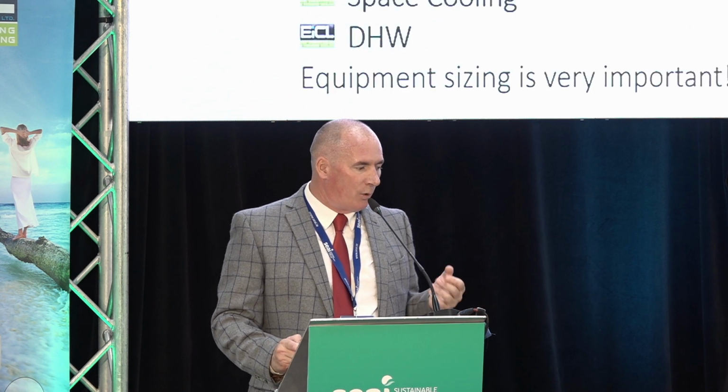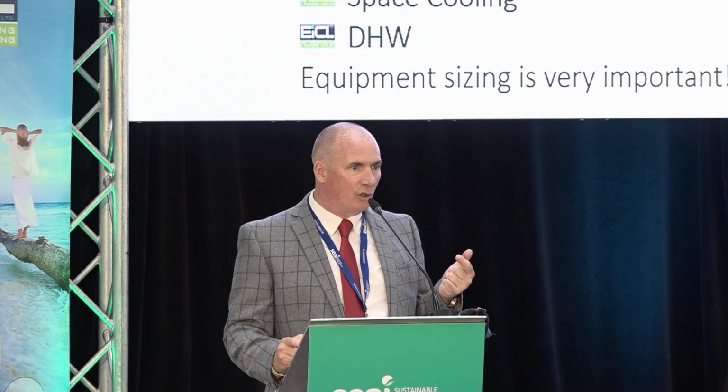Very often when we're talking to consulting engineers when they're designing a new building, we want to know the heating load, the cooling load, so space heating, space cooling, and domestic hot water, the things that we need to satisfy with our heat pump technology. When we have this information, we can be a little bit more intelligent about how we select equipment. Historically, if you had 100 kilowatts, you'd select 110 kilowatts, what you want plus a bit, or maybe two, half the size or something like that.